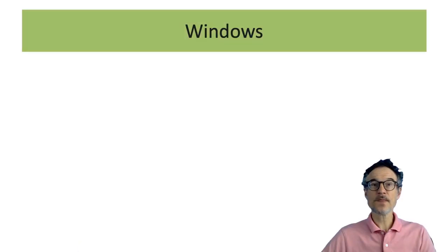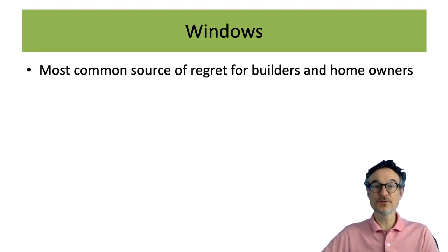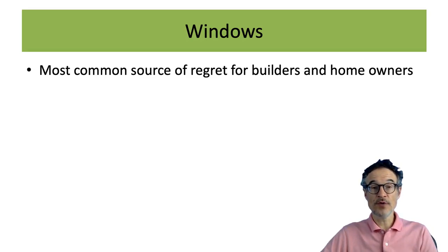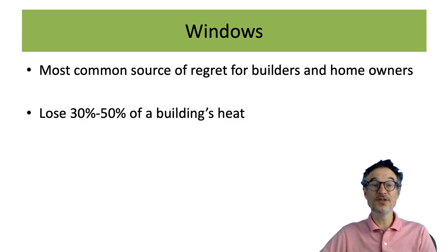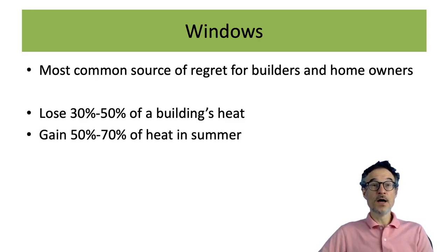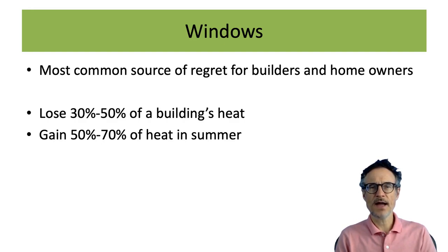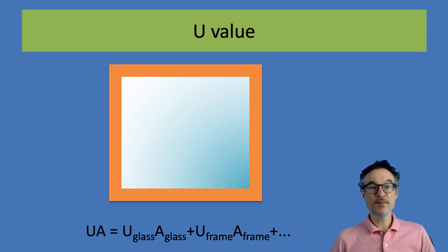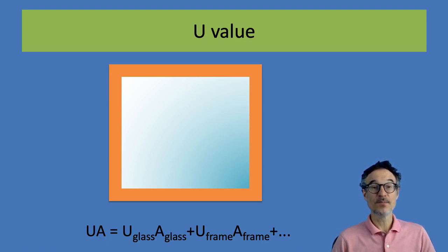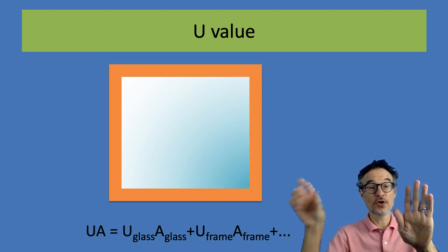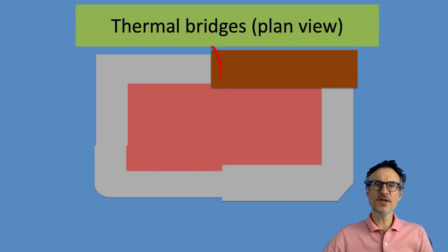Windows are the most common source of regret for builders and homeowners — they wish they had a window in a different place or a different kind of window. As we've seen, something like 30 to 50% of a building's heat is lost through windows, and in the summer windows can gain a lot of heat. We need to think carefully about where to put them and which windows to use. For window performance we want to look at the U-value, which tells us how much heat that window is going to lose.